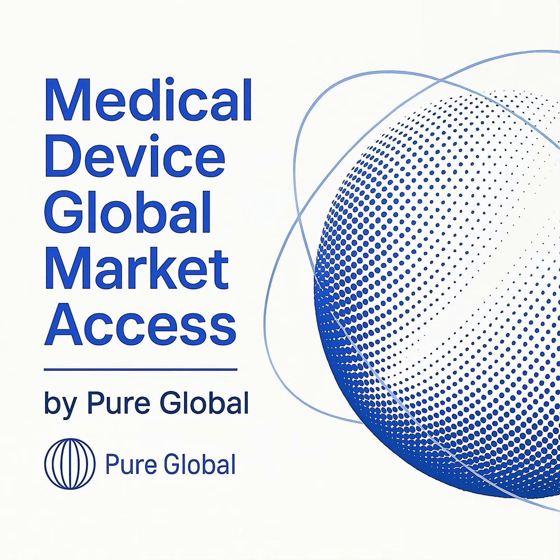A fundamental concept within Part 812 is the distinction between two types of device studies, those involving a significant risk device and those with a non-significant risk device. The classification dictates the regulatory path forward. A significant risk, or SR, device is defined as one that presents a potential for serious risk to the health, safety, or welfare of a subject.